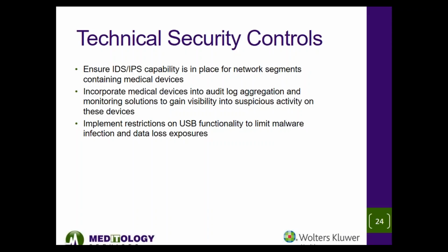And then if you do nothing else, I laugh about this USB one. Quick anecdote, we had a vendor that kept getting infected with this computer worm, a really nasty computer virus, and it kept spreading to that device and then to the rest of the network. And every time we came back, and these same devices were getting infected, it turned out the service person that came in to service the devices was bringing an infected USB device. Every time he came, like every week literally, to service the device, he would plug his infected USB in and reinfect the system because it wasn't patched and it wasn't up to date.